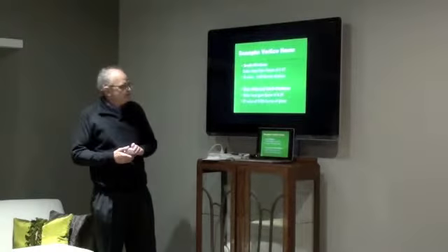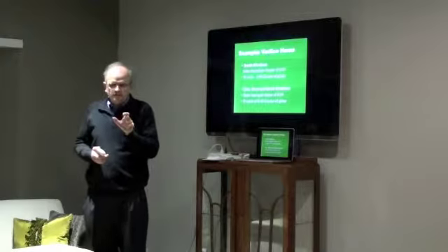Catherine did some sleuthing and got the exact figures for it. So on the south windows here, we're running a solar heat gain factor of 0.57, and the center of the glass R value is 5.88. And that's roughly equivalent to 2 inches of glass fiber insulation. So these are quite energy conserving windows here.